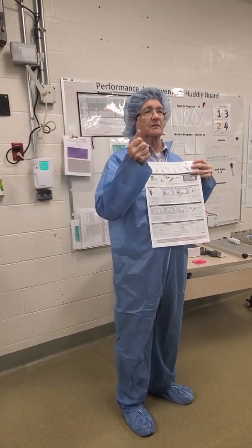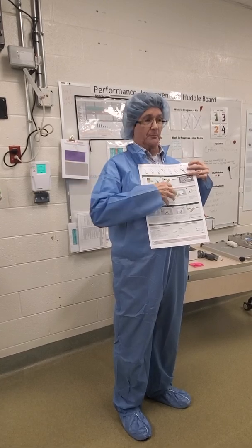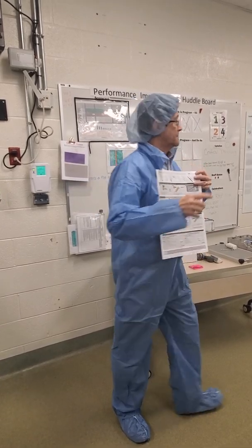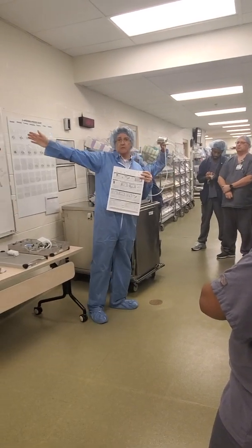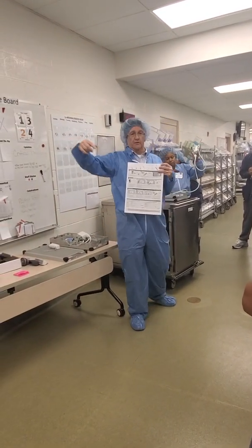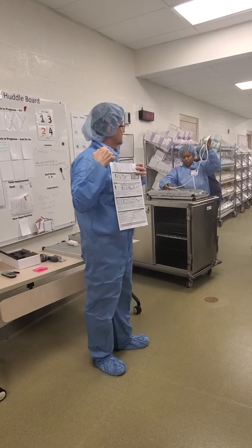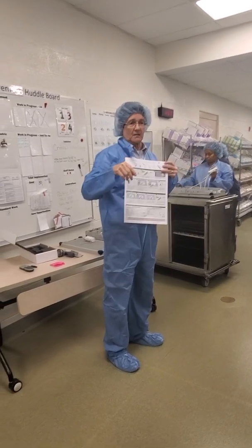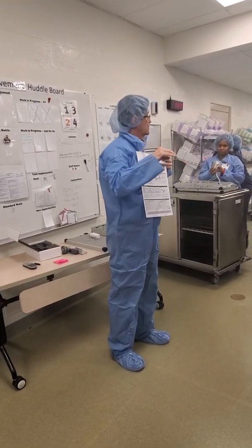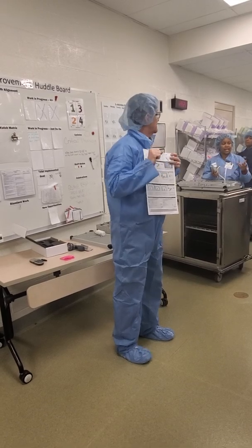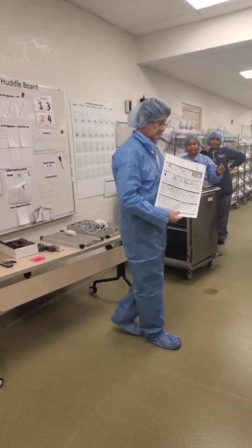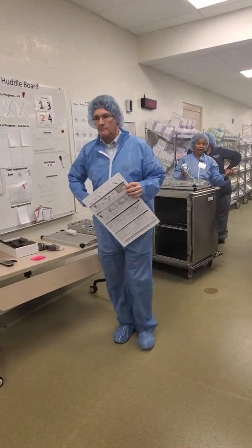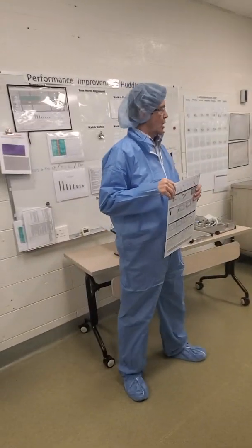Make sure it doesn't leak here before you put the probe in the water. Because if it leaks and you see it leak, don't put it in the water. Because water can get in from wherever it's leaking, right? So if no water gets in, it's probably repairable. So just like the endoscopes, you do a dry and a wet leak test, you do a dry and a wet for these ultrasonic probes as well.